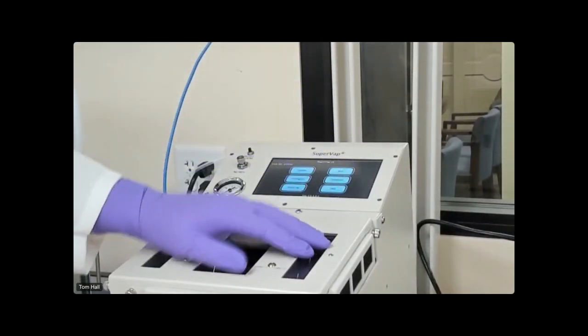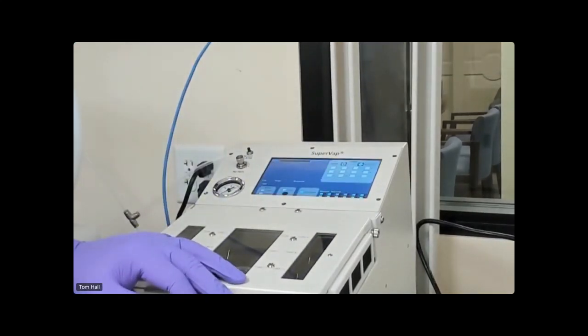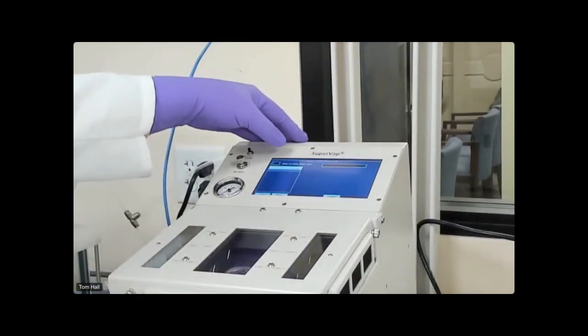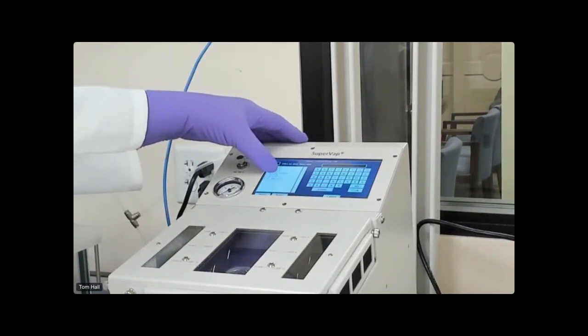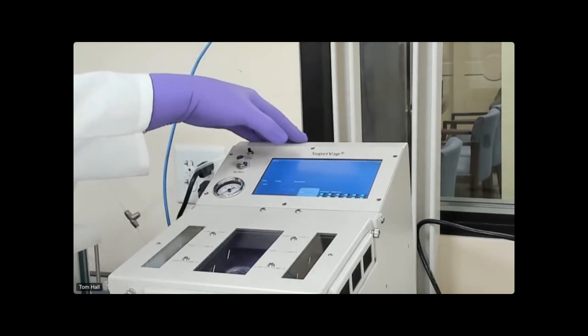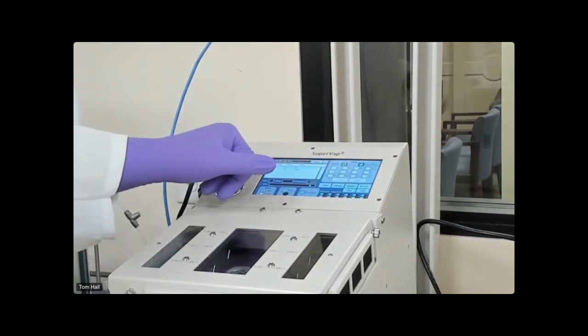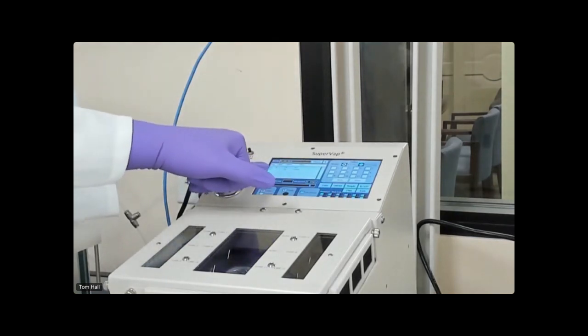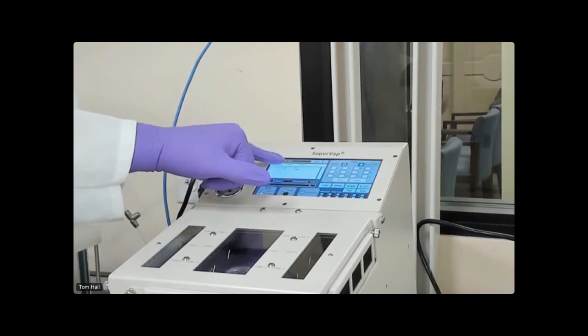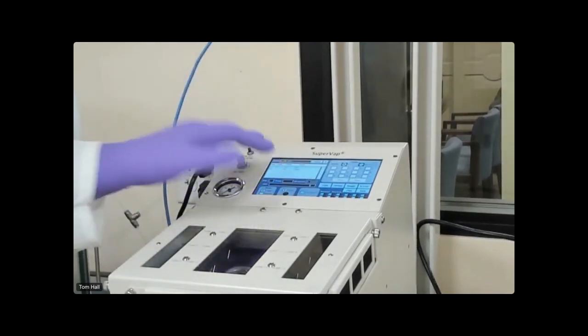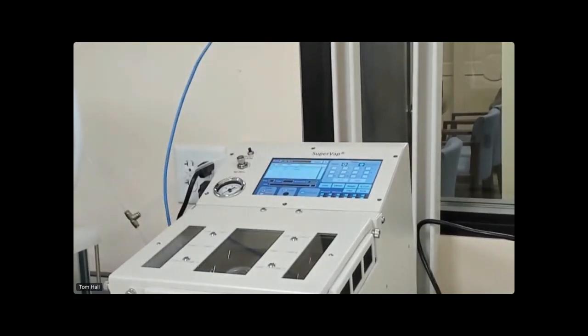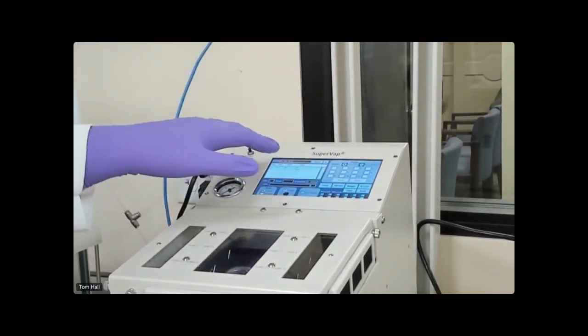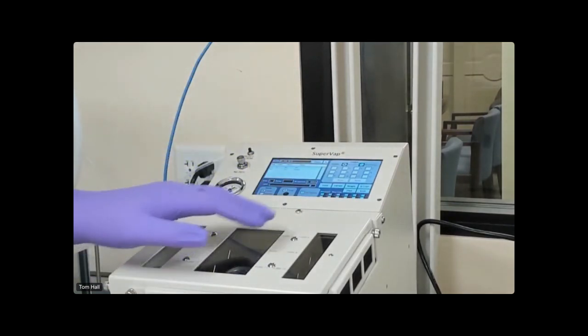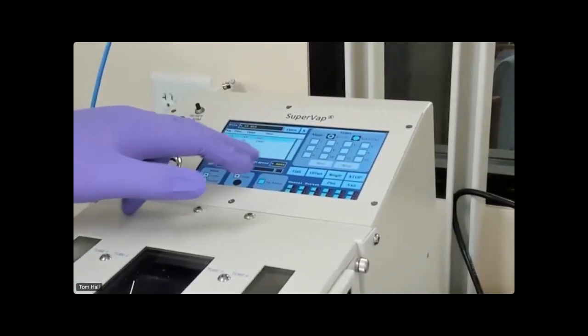So this is the top of the screen for regulation. It comes with pre-programmed temperatures. For instance, let's say that I choose 50 degrees to blow down my samples. Then you have a heating up step and a constant temperature step. In this case, it would heat up first to 43 degrees, and then after that, it stays for 3 minutes here. After that, it goes to step 2 where it heats to 50 degrees and stays there. Once each sample is down to the final volume, the alarm for that particular position will sound. You can also see here the elapsed time and the temperature.